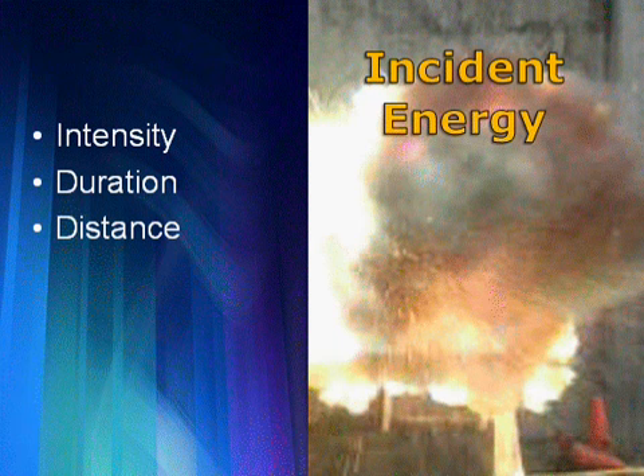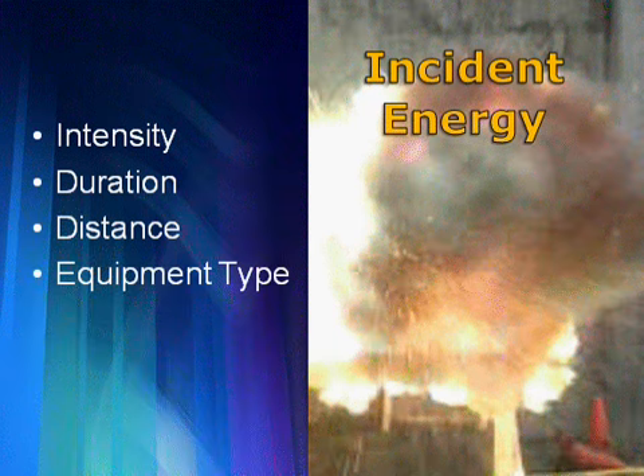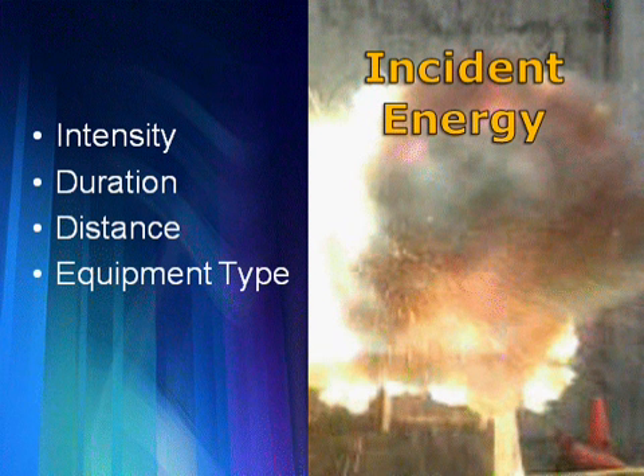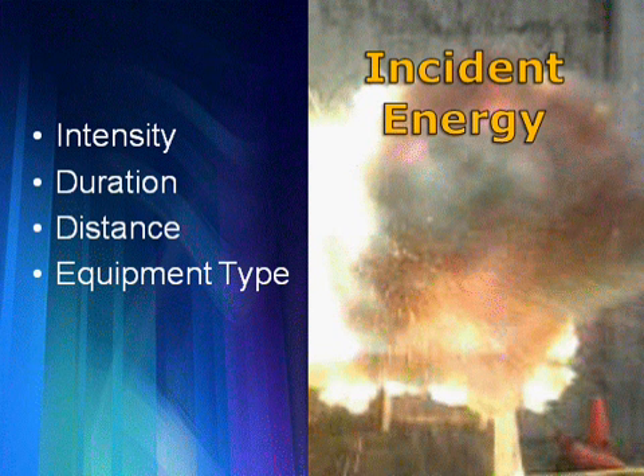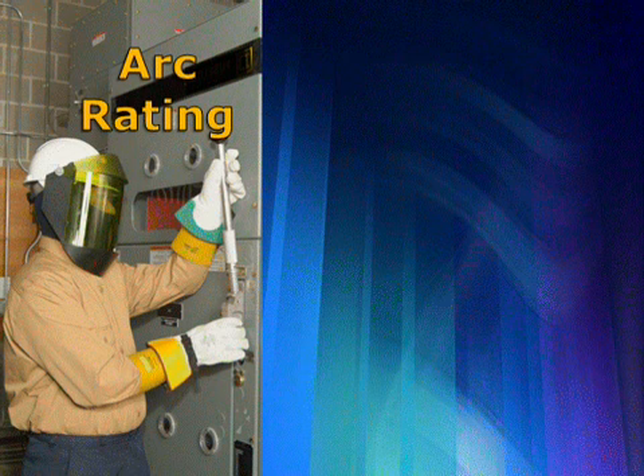The distance, it's also going to be dependent on the distance from the prospective arc, and also the equipment type. And the equipment type has a lot to do with it. If you have an arc flash out of a panel board, for example, versus an arc flash out of switchgear, they behave a little bit differently. In the IEEE equations is something known as an X-distance factor, and that is just a way to predict that if you have an arc flash in a panel, it comes out a certain distance, and if you have it within a switchgear, it comes out a little bit harder, and standing at the same distance, you may have different incident energy. So the equipment type is very important in this as well.